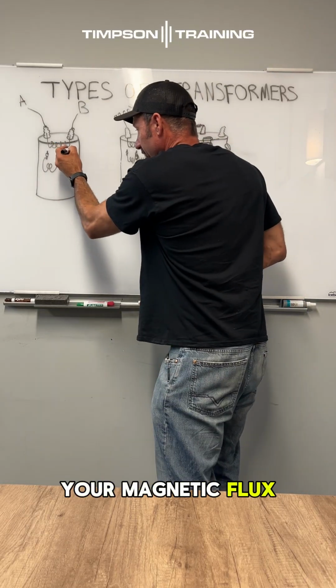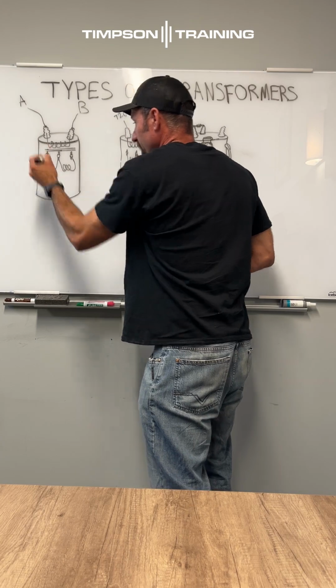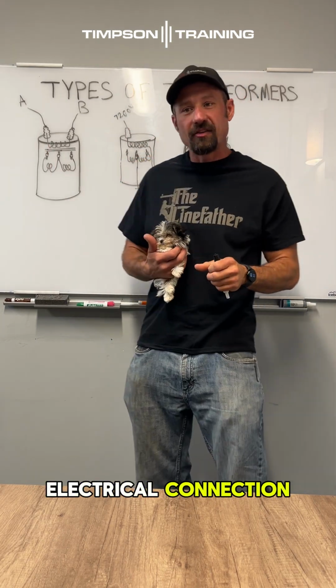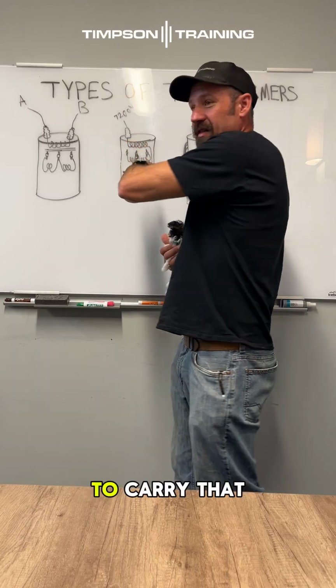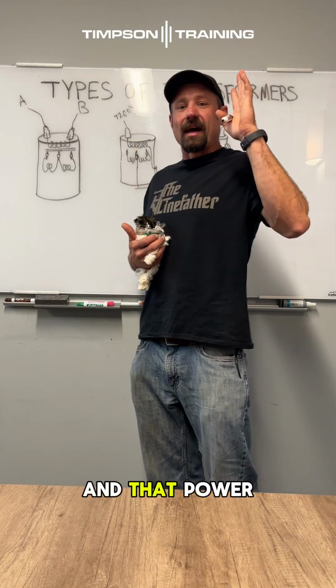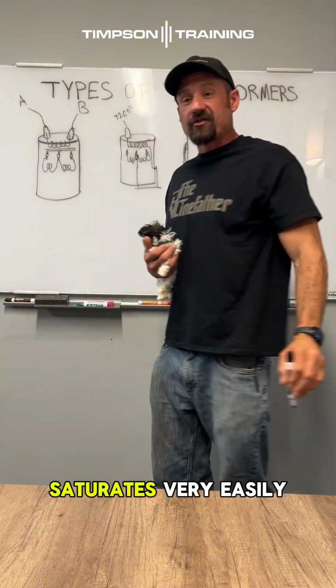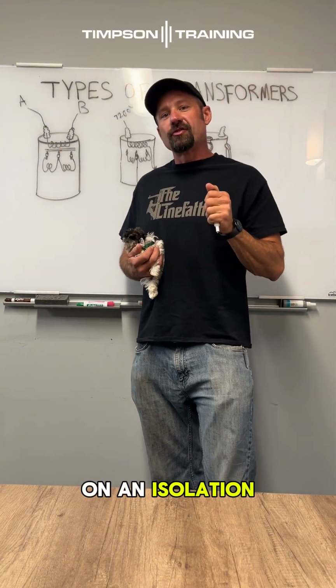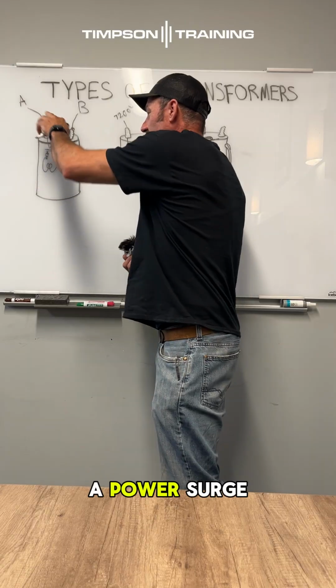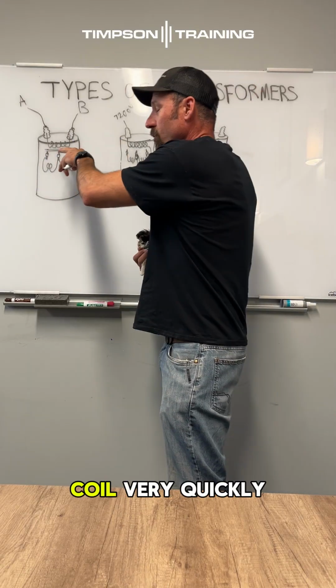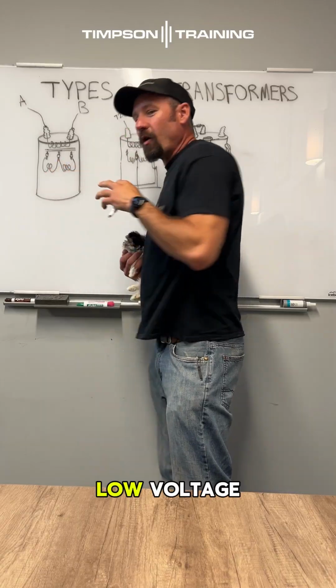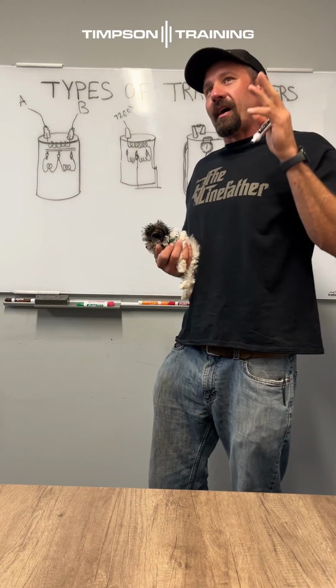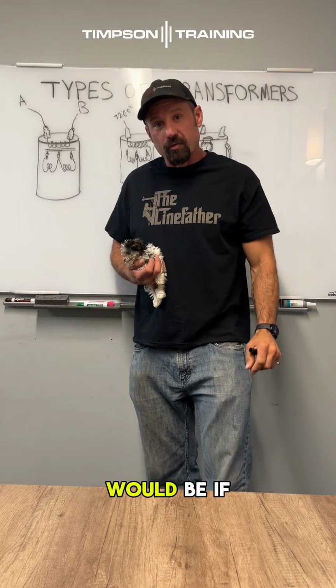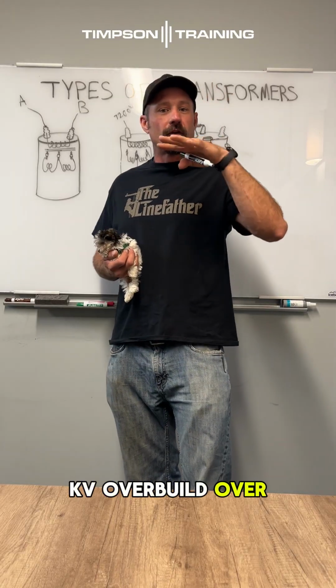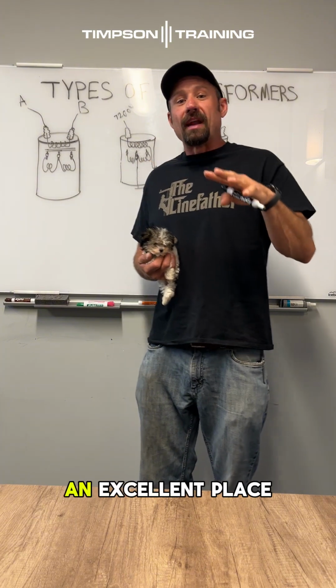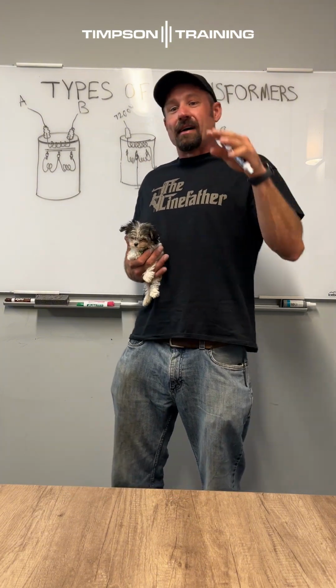So your magnetic flux that's traveling through this core is all just that. There's no electrical connection to help make a perfect highway to carry that fault current and that power surge through. This core saturates very easily. On an isolation transformer, if you put a power surge into this top side, it saturates the coil very quickly. So you end up getting a low voltage out of the secondary side. A good place for isolation transformers would be if you have 34 kV overbuild over top of 12 kV. That would be an excellent place to have isolation transformers.